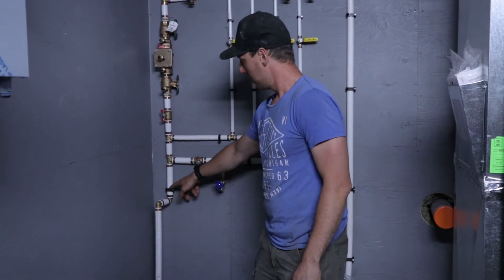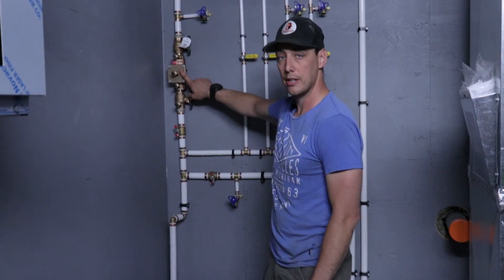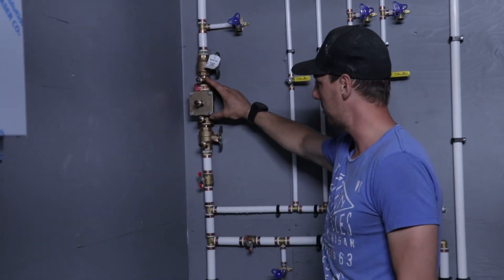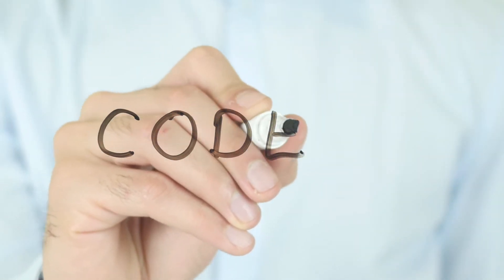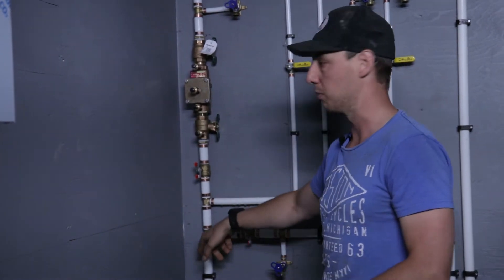We have a one-inch line that comes straight up to a dual check valve. It's a testable device, and it's code for us to have them for irrigation. This prevents dirt from coming back in and getting into your domestic water.